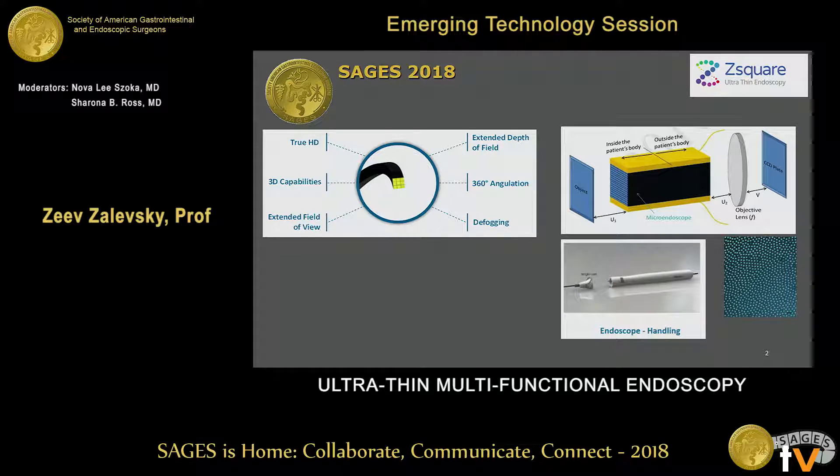Because we have such a large number of cores, we can allow very high resolution in a very small cross section. If we add more and more square structures, we can enhance other features like extending the depth of field, extending the depth of focus, and adding three-dimensional capabilities. Because the endoscope is so thin, we can also prevent fogging by using only very small power of heating for the tip.